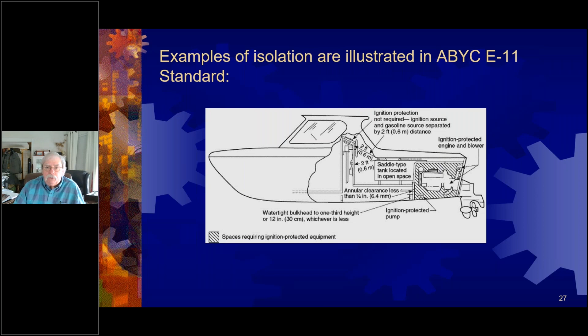GFCI devices are required on weather decks, engine room spaces, galleys, and heads. But keep in mind the GFCIs we use are not rated for ignition protection, and they have a very high failure rate in marine applications. They're the same grade as the ones in your house, and the marine environment is such that they will eventually corrode in place and stop functioning.